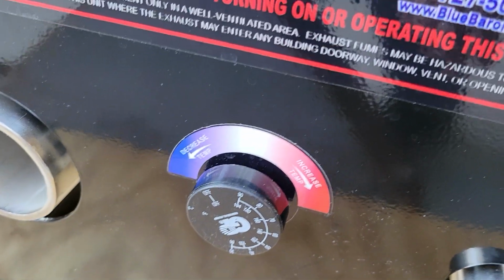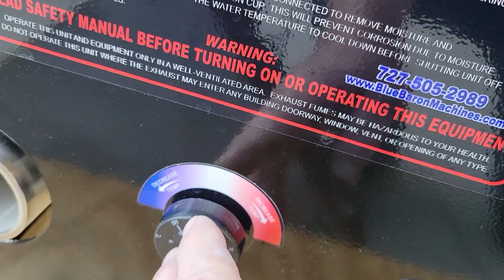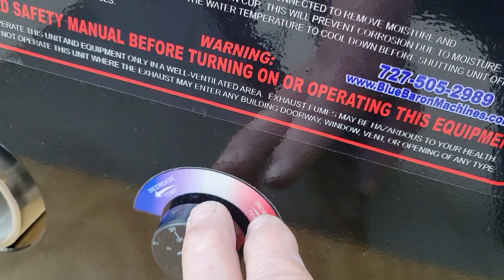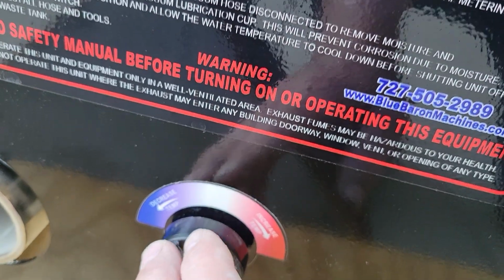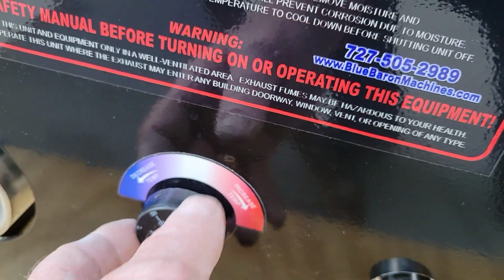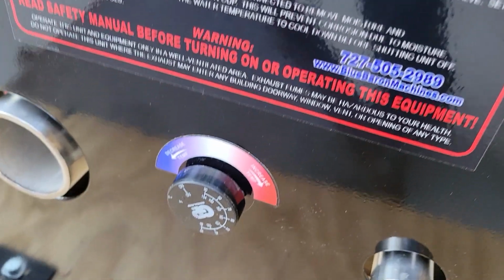Underneath the undercarriage, there's a wire that connects to your common, 12 volts, and then it's a normally open switch. It will close when it reaches the desired setting, sampling the temperature right there of that probe capillary, and then it'll tell it to turn on.